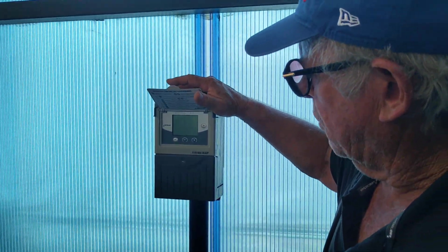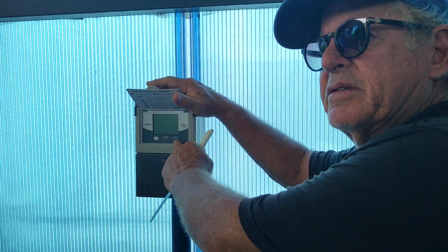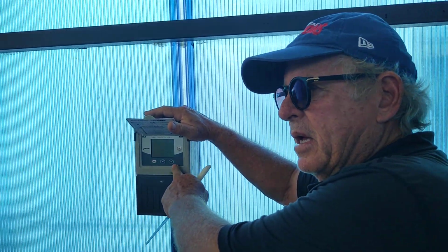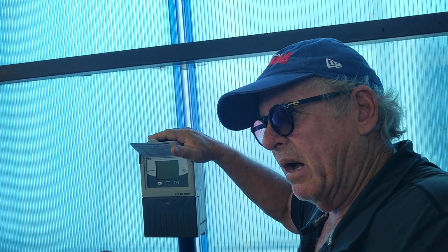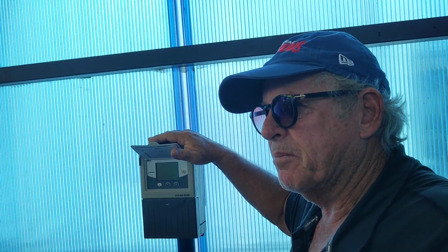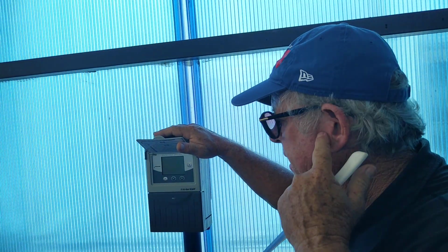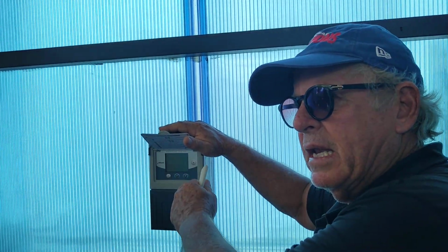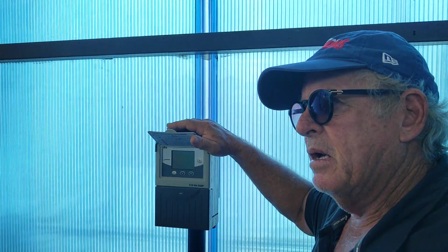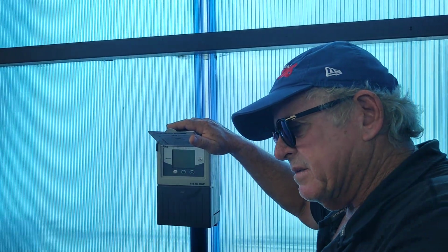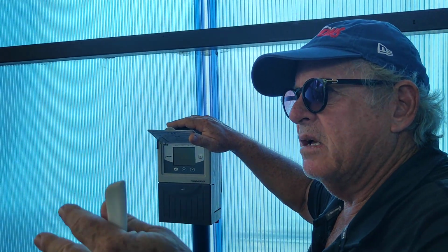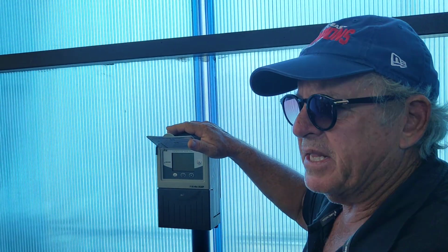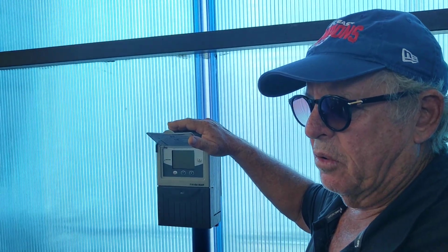With this backflush control, I can set up the time to tell it that when the difference in the pressure, let's say, is 1 bar, start the process. And I can also tell it to give some backup, saying that if there is no backflush during the last 4 hours, make it by time. It's an automation system.